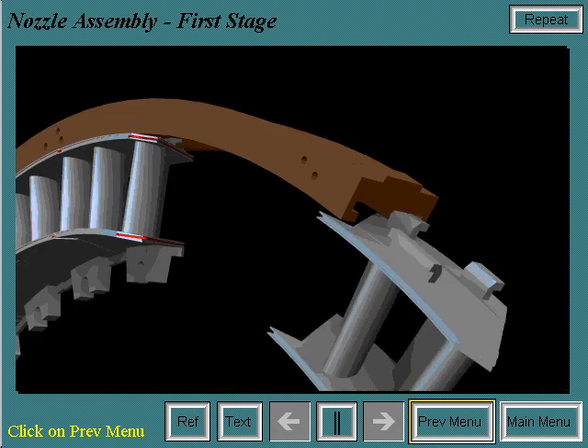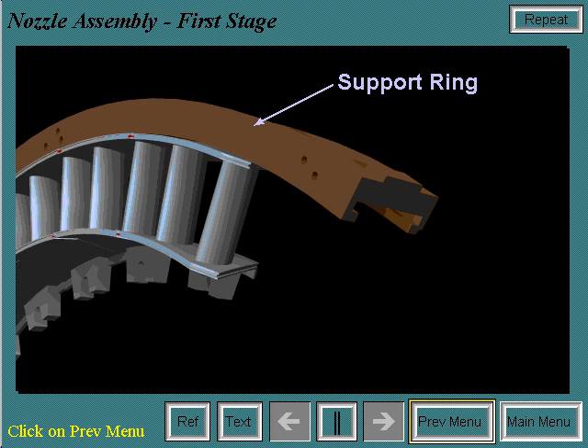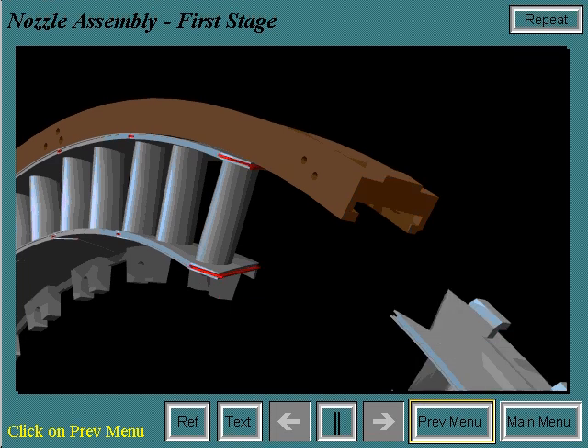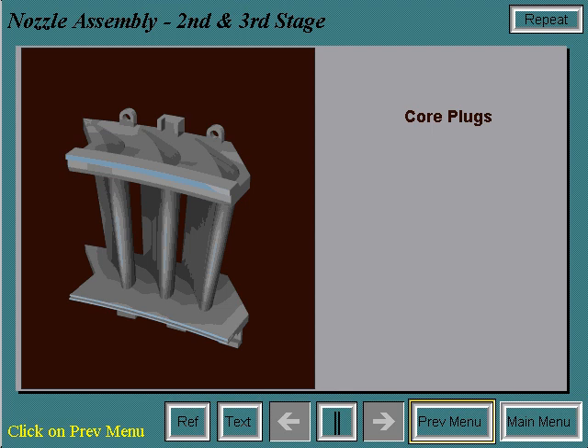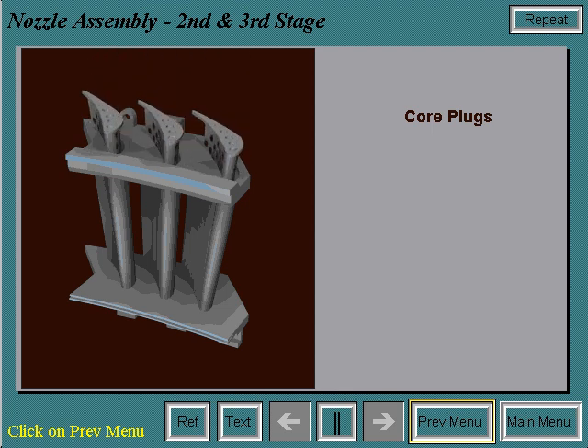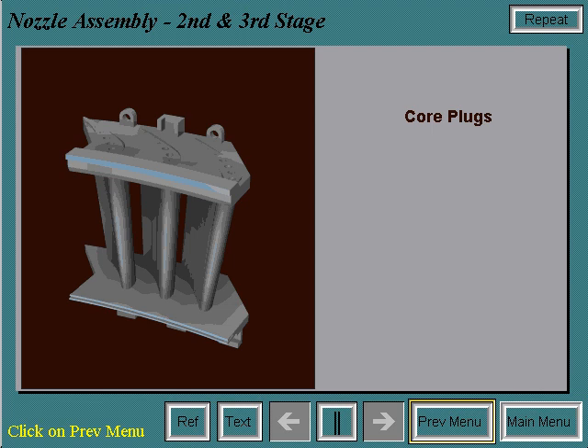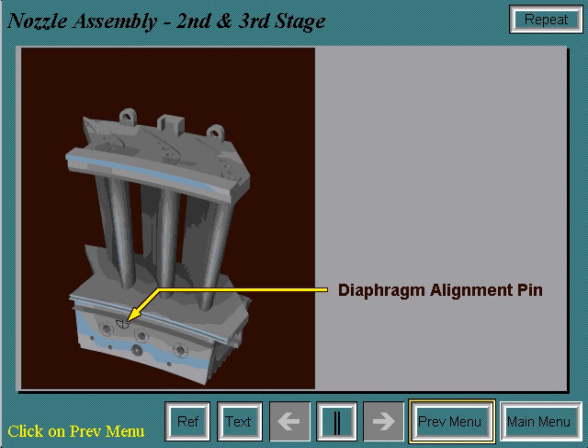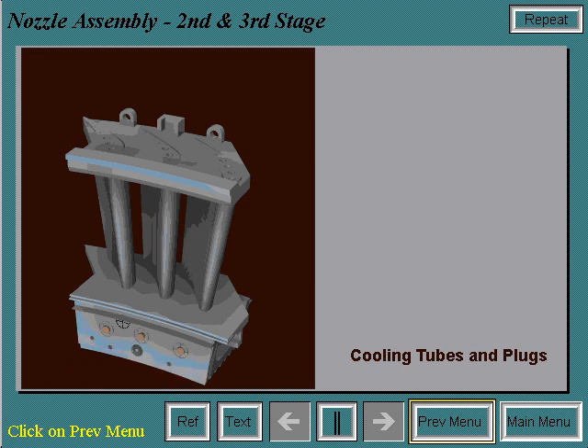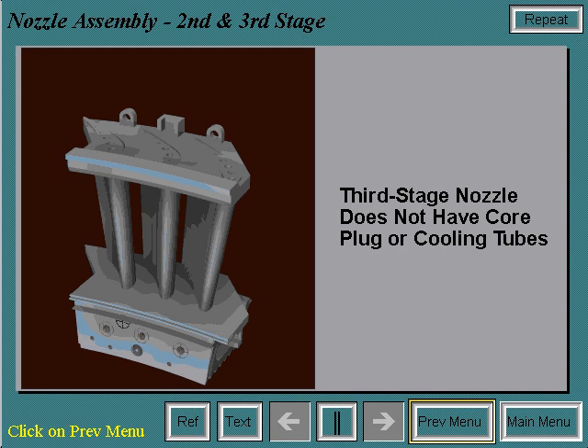To assemble the first stage nozzle, the nozzle segments are installed into the support ring. Alignment pins are then installed to radially align the segments in the ring. To assemble the second stage nozzle, first a core plug is installed in the investment cast piece to allow for even cooling down the center of the bore of the nozzle segment. The diaphragm section is then attached and a pin is installed for nozzle-to-diaphragm alignment. Wheel space cooling tubes and plugs are installed in the diaphragm. The third stage nozzle is similar to the second stage nozzle, but it is not forced air cooled, so there is no core plug and there are no cooling tubes.